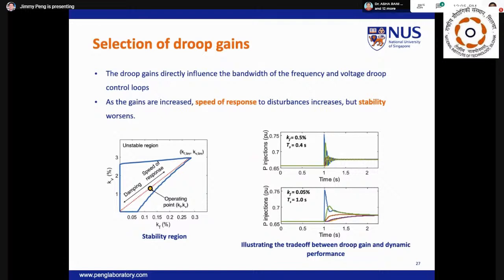Referring to the stability region plot illustrated on the left-hand side of the slide, the combination of KF and KV gains can actually push the system to stability by ensuring sufficient damping performance, or accelerating the response speed at the cost of driving the microgrid to instability. This is evident in the 2 time domain plots shown on the right-hand side, where a settling time of 0.4 seconds will generate more violent oscillatory dynamics than a system with a settling time of 1 second.